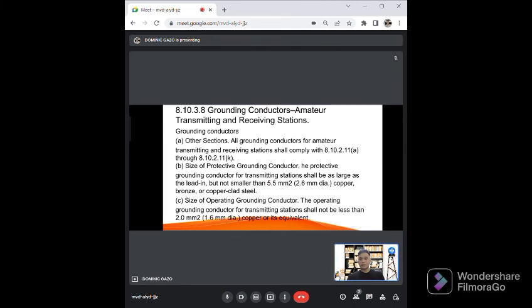For Article 8.10.3.8, grounding conductors for amateur transmitting and receiving stations. For grounding conductors, all grounding conductors for amateur transmitting and receiving stations shall comply with 8.10.2.11(a) through 8.10.2.11(k). And for B, size of protective grounding conductor. The protective grounding conductor for transmitting stations shall be as large as the lead-in, but not smaller than 5.5 mm squared or 2.6 mm diameter. For size of operating grounding conductor, the conductor for transmitting stations shall be not less than 2 mm squared or 1.6 mm diameter.